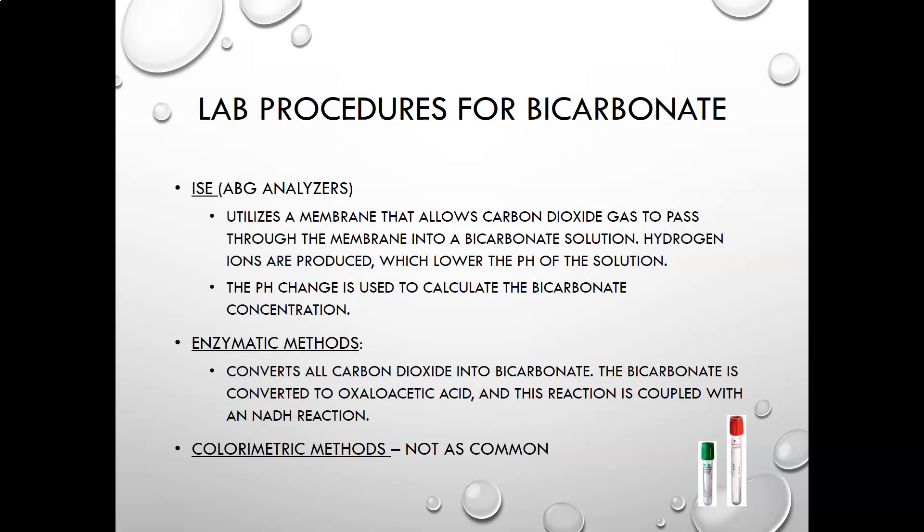The procedures to measure bicarbonate: ABG analyzers usually use an ion-selective electrode where the membrane allows CO2 gas to pass through into a bicarbonate solution, producing hydrogen ions that lower the pH of the solution. That pH change is used to calculate the bicarbonate concentration, so it is a calculated value based on the pH. The enzymatic method — used on most large analyzers that run BMP and CMP panels — converts all carbon dioxide into bicarbonate, then converts bicarbonate to oxaloacetic acid. That reaction is coupled with an NADH reaction, which is measured and is proportional to the bicarbonate concentration.